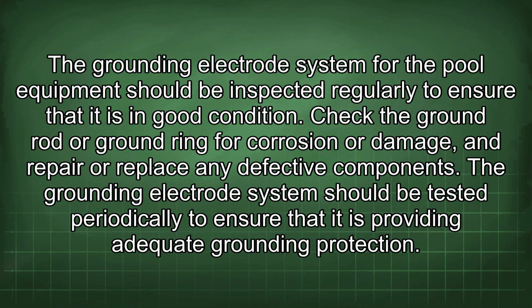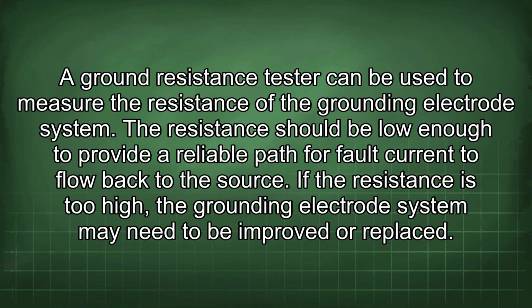The grounding electrode system for the pool equipment should be inspected regularly to ensure that it is in good condition. Check the ground rod or ground ring for corrosion or damage, and repair or replace any defective components. The grounding electrode system should be tested periodically to ensure that it is providing adequate grounding protection. A ground resistance tester can be used to measure the resistance of the grounding electrode system. The resistance should be low enough to provide a reliable path for fault current to flow back to the source. If the resistance is too high, the grounding electrode system may need to be improved or replaced.